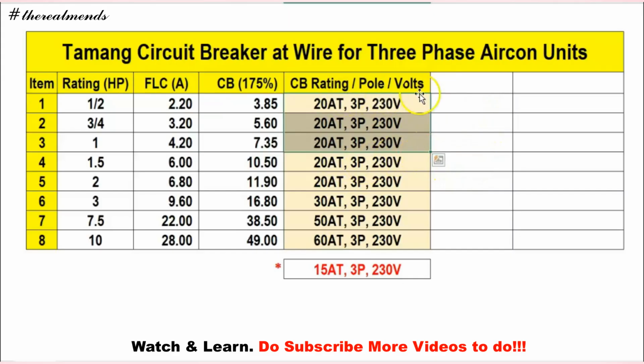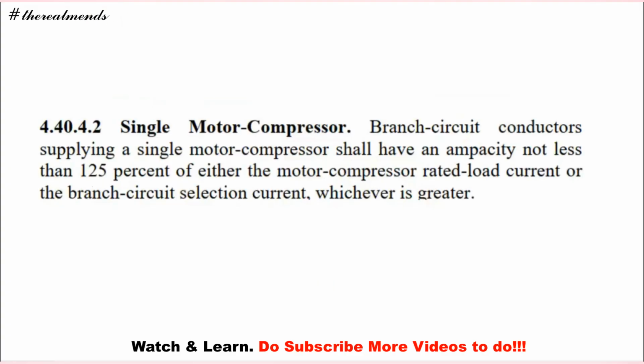Let's proceed for the yung wire o yung conductor. Again, from the table, 4.40.4.2 for a single motor compressor. So, yung branch circuit conductor supplying a single motor compressor shall have an ampacity not less than 125% of either motor compressor load current. So, yung kanyang conductor daw, merong factor na 125%. So, ito yung ating gamitin to size up yung magiging wire ng aircon units natin.